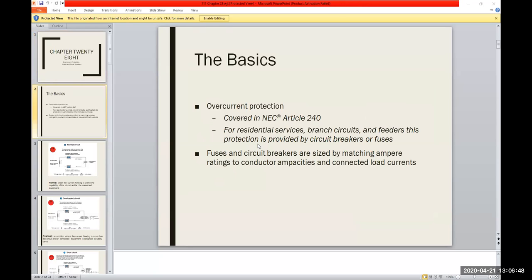they are required on every feeder line, and you'd have to have them for residential services. Any branch circuits have to have circuit breakers or fuses. Now, in the old days, I actually had some of those in the lab, and this is how it was when I grew up too, they had the old screw-in fuses. Each branch circuit is rated, so you have the corresponding fuse. Back then, with those screw-in fuses, I don't even know why these were allowed to be sold, but every fuse size had a different bore, a different diameter. So a 15 was a certain diameter, so you couldn't mix and match or by accident put on the wrong one.